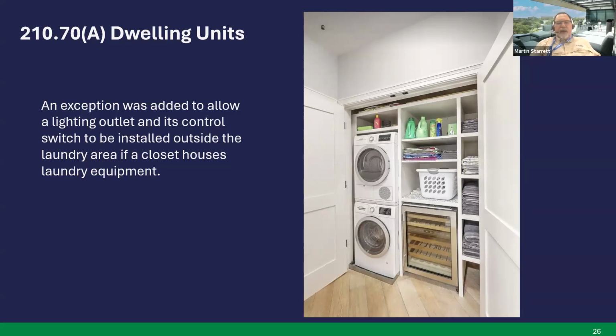So it was added to allow a lighting outlet and its control switch to be installed outside the laundry area if a closet houses laundry equipment. That makes sense because you wouldn't have been able to put it up in there anyway. But I'm sure there were probably some discussions between installers and inspectors like, well, it says the laundry area, you got to put it in there. And well, I can't. Can I put it here? Well, no, it says you got to go in there. Kind of clears up a lot of that enforcement issue. We'll see a lot of that in the 2026 as well.